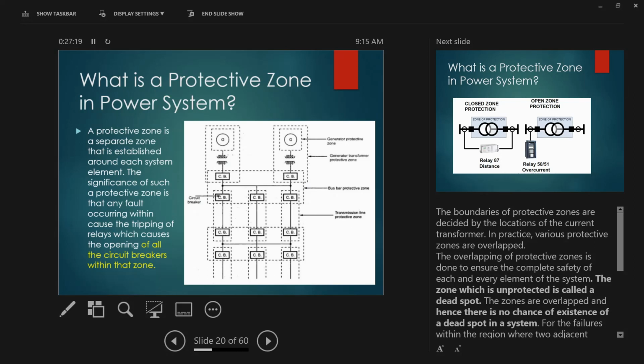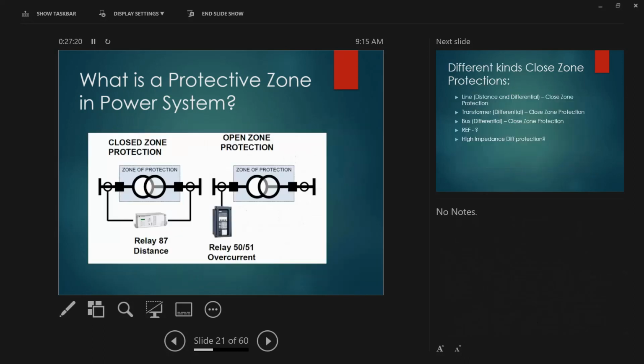So that's the industry that we are normally doing the maintenance. So what is the protective zone in a power system? There is a closed zone protection, which is the differential. It doesn't care about the overcurrent. It only cares about the internal fault of the transformer. That is the closed zone protection.